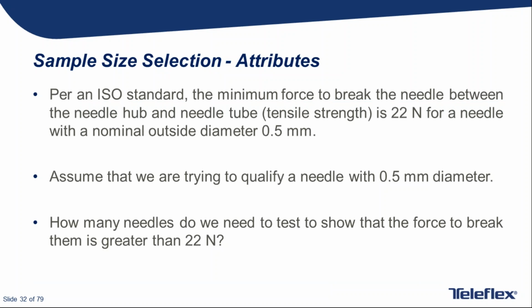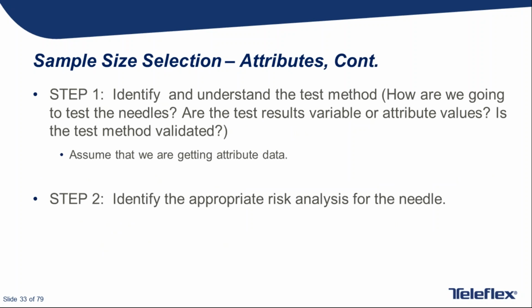So here's an example. The minimum force to break the needle between the needle hub and needle tube is 22 newtons for a needle with a nominal outside diameter of 0.5 millimeter. How many needles do we need to test to show that the force to break them is greater than 22 newtons? So we're going to assume we're doing attribute testing at first here, and this will be a straightforward example, as I'm sure you statistics people realize already. All we're doing is counting how many needles pass and how many fail during the testing.